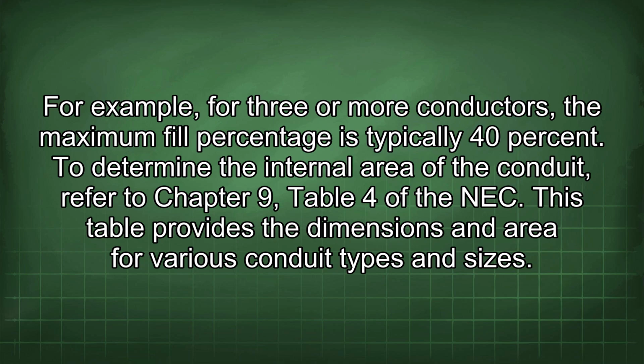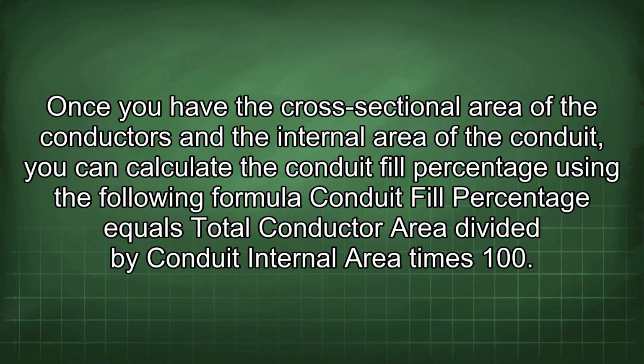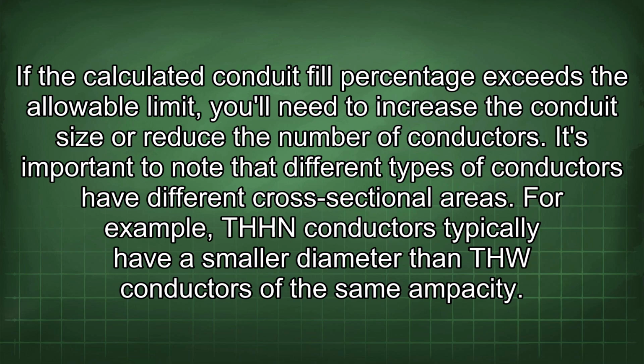To determine the internal area of the conduit, refer to Chapter 9, Table 4 of the NEC. This table provides the dimensions and area for various conduit types and sizes. Once you have the cross-sectional area of the conductors and the internal area of the conduit, you can calculate the conduit fill percentage using the following formula: conduit fill percentage equals total conductor area divided by conduit internal area times 100.